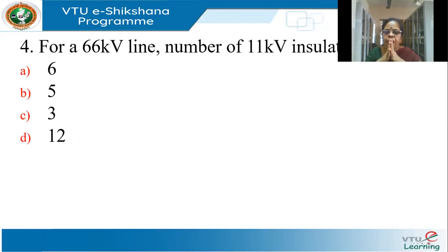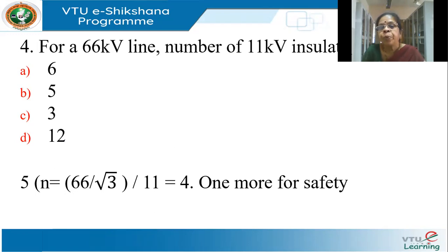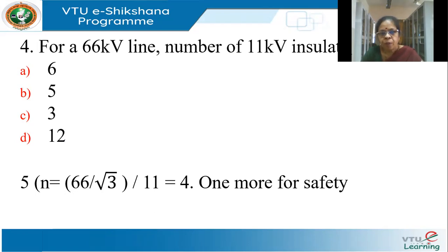For a 66 KV line, how many 11 KV insulators do you use? You might be tempted to write 6 — don't. The answer is 5. For a 66 KV line, 66 KV is the line-to-line voltage. In a three-phase system, the voltage across an insulator is the line-to-neutral voltage. So convert: 66 divided by root 3, then divide by 11, which is approximately 4. So 4 discs are enough, plus one extra for safety — giving 5.